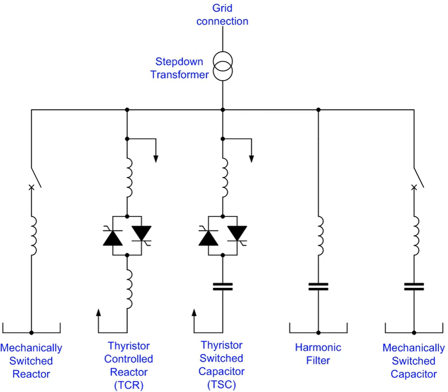Typically, an SVC comprises one or more banks of fixed or switched shunt capacitors or reactors, of which at least one bank is switched by thyristors. Elements which may be used to make an SVC typically include: thyristor-controlled reactor, TCR, where the reactor may be air or iron cored; thyristor-switched capacitor, TSC; harmonic filters; mechanically switched capacitors or reactors switched by a circuit breaker.